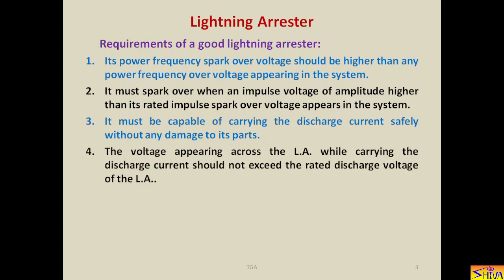Number 4, the voltage appearing across the lightning arrestor while carrying the discharge current should not exceed the rated discharge voltage of the lightning arrestor. This discharge voltage is also called the residual voltage of the lightning arrestor. So when the lightning arrestor is discharging, the lightning over voltage current is flowing. So there is resistance of the lightning arrestor, normal resistance plus nonlinear resistance. So voltage is developing across the lightning arrestor and this voltage is also appearing across the equipment being protected. So in no case should this voltage exceed the rated discharge voltage of the lightning arrestor. So the lightning arrestor must be tested for the discharge voltage also.